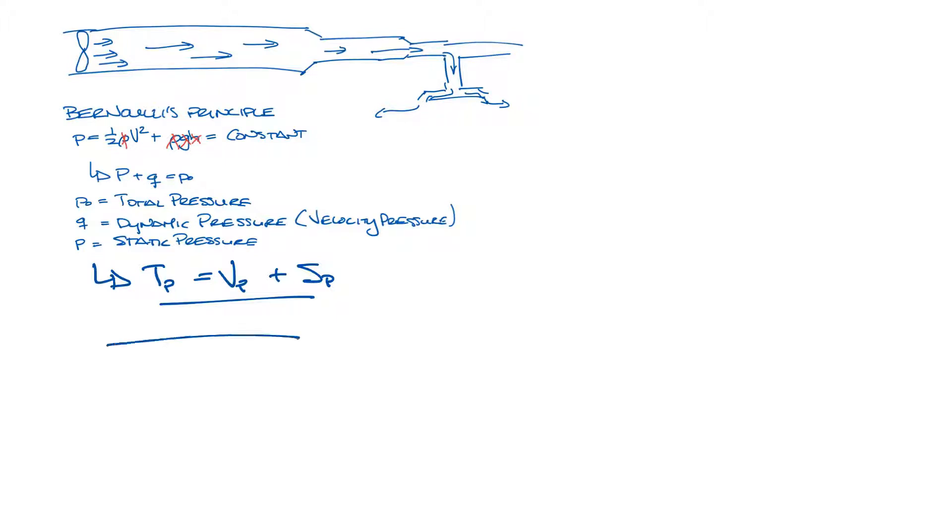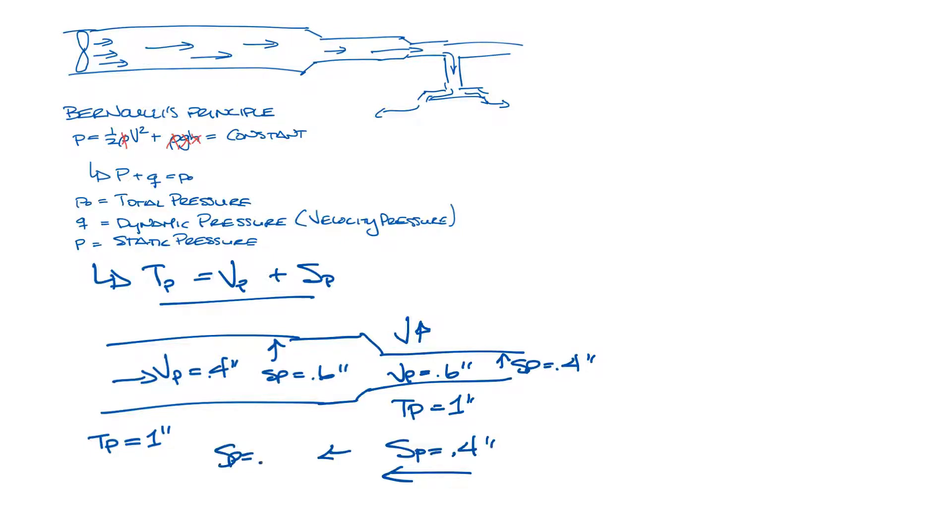So when we have a piece of ductwork, and let's say we have one inch of total pressure, and let's say it's made up of 0.4 inches of velocity pressure and 0.6 inches of static pressure. When it transitions to a smaller section, assuming no friction, your total pressure will stay one inch, but now maybe your velocity pressure went to 0.6 because it sped up, and your static pressure went to 0.4. Or the opposite is true if the airflow is moving in this direction. So maybe your static pressure would go from 0.4 to 0.6, and this is called static regain.